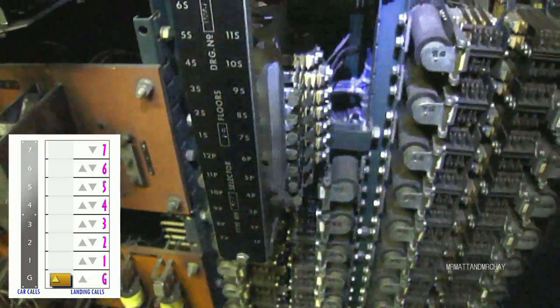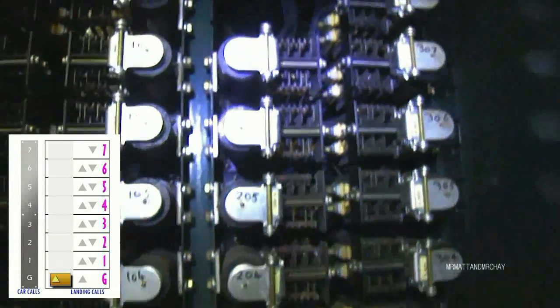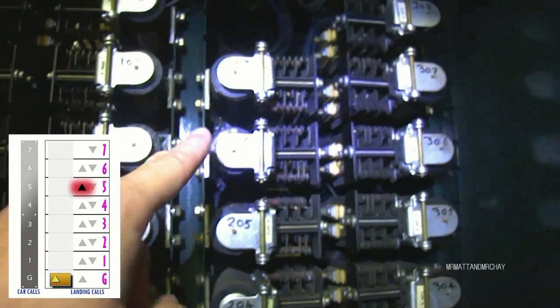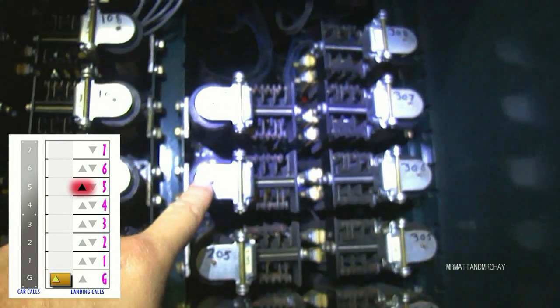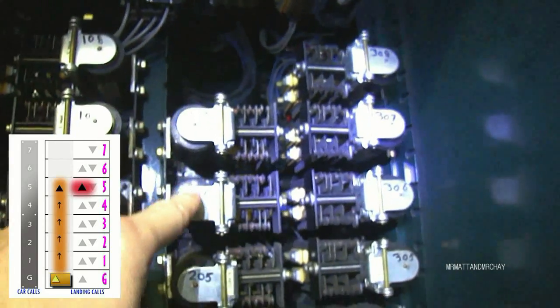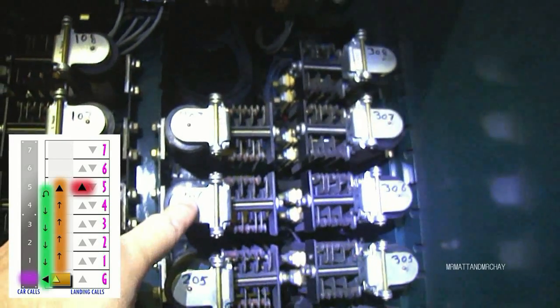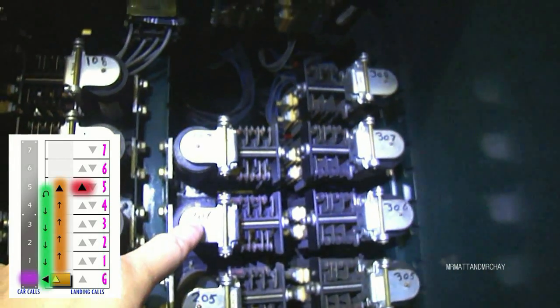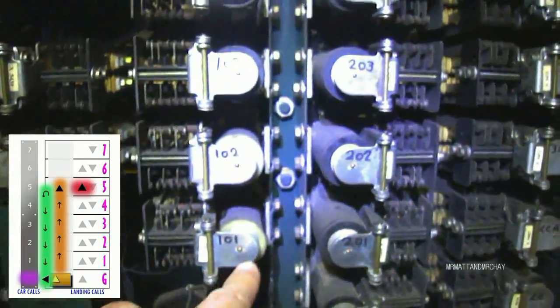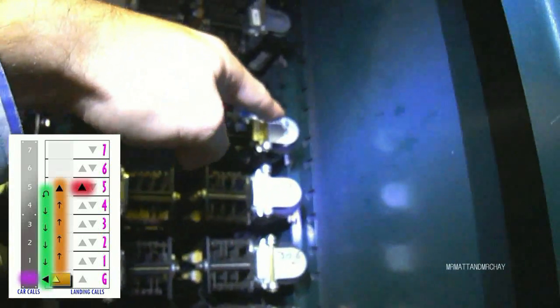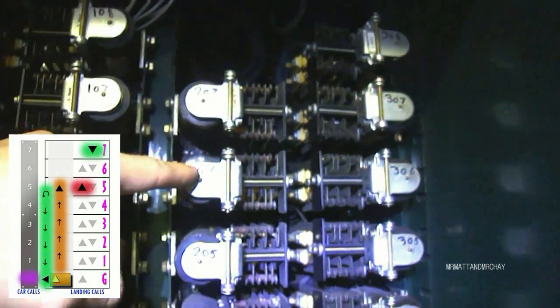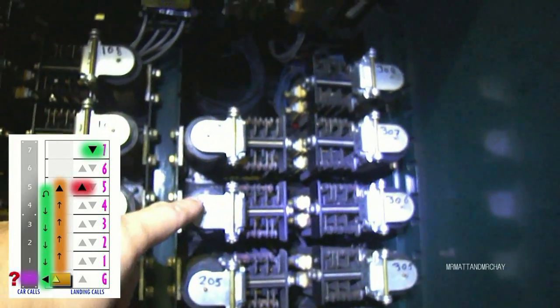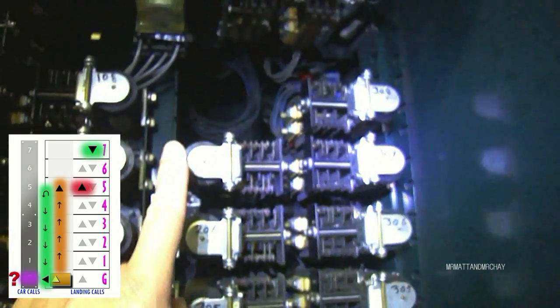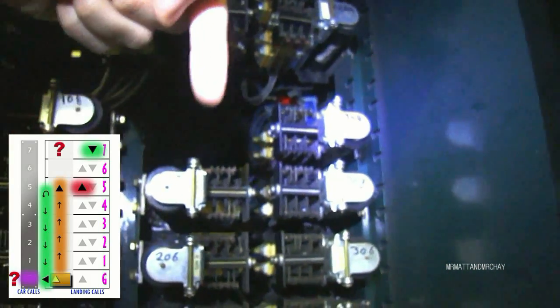Next experiment. I'm now going to make an up call on the fifth floor. The lift is then expecting to go up to one of these floors. But when someone gets in, they're actually going to push the ground floor. I'm going to press that button there. Just after I press that one, I'm going to give it a down call above the lift. Now the question is, will the lift obey the car call for the ground floor, or as it's still a collective state up, because I pushed the up button on this floor, will it continue up to get the top floor and then come back down?